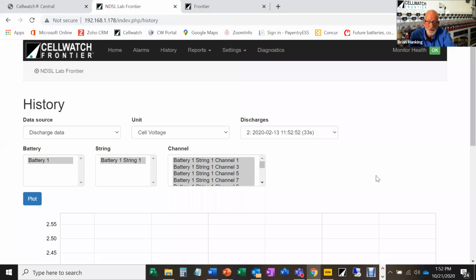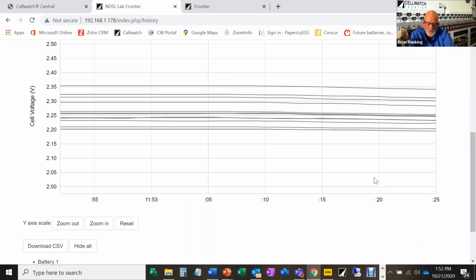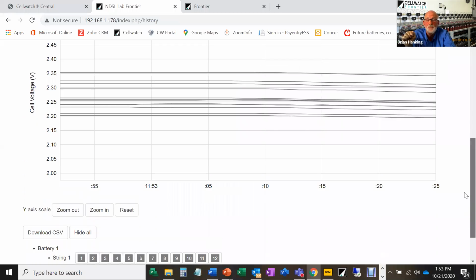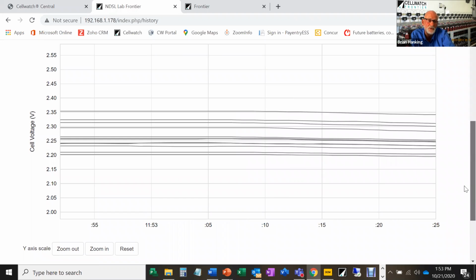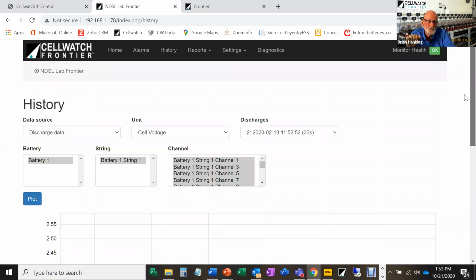We can also download this data through the CELLWATCH Central, which I showed you earlier. This is a very brief 33-second discharge, but it shows the performance of the cells. If any cell falls out, it usually happens in quite a short time, and over the course of a string of batteries you may not notice—it might just look like a small voltage drop of 2 volts in a voltage that's dropping anyway, so it's very difficult to detect. If you look at them individually, you can see them drop out quite easily. So discharge files are very useful for that.